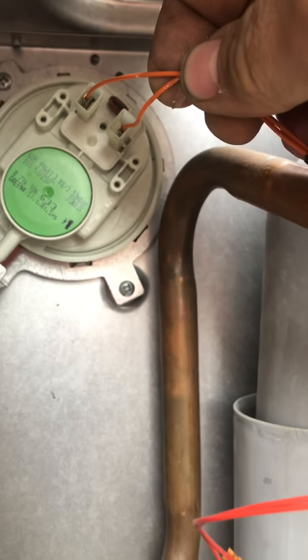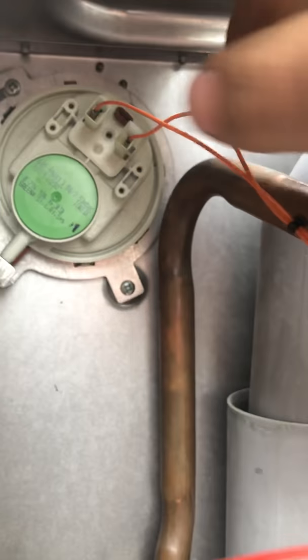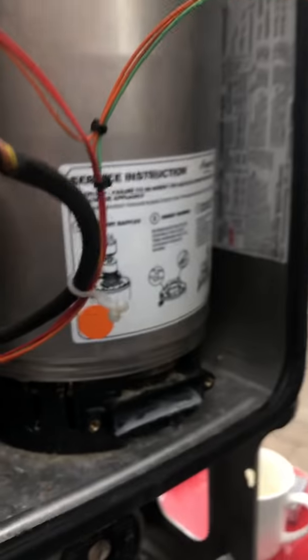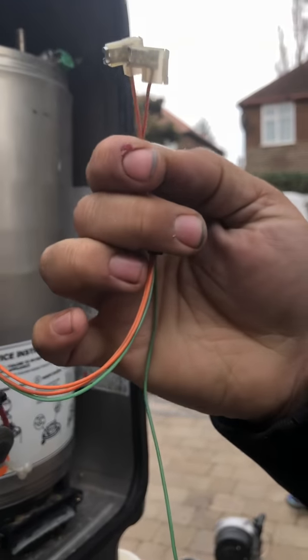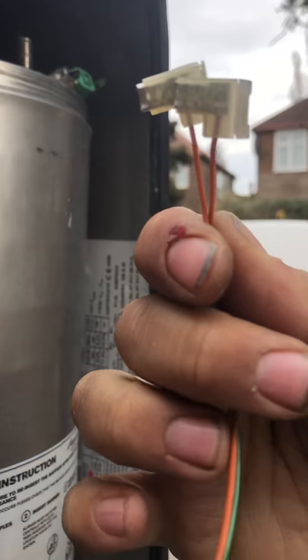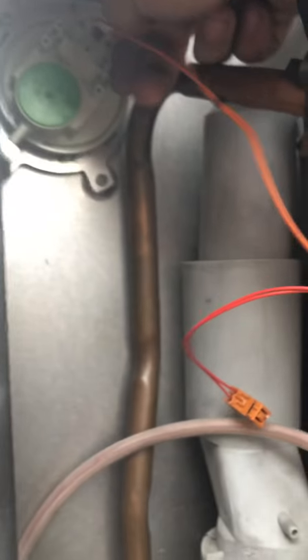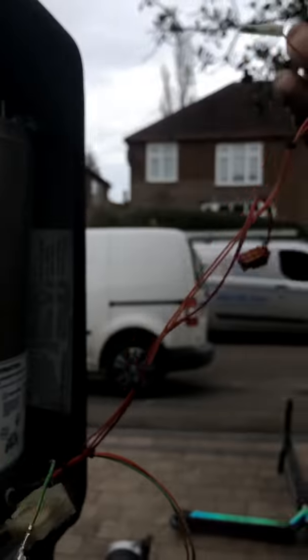And the other orange wires, they go up to the air pressure switch. Now you can't get them wrong, because number one, they have a different connection on them, okay? And number two, the other wires wouldn't be able to reach up to the air pressure switch. So we'll get that one off and that one off. So it's not as complicated as you think.